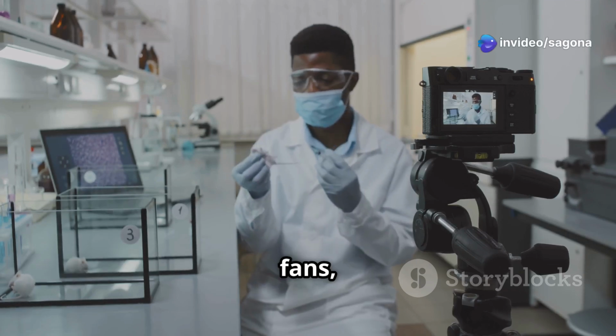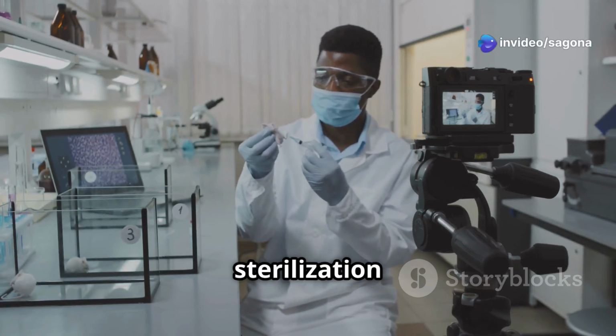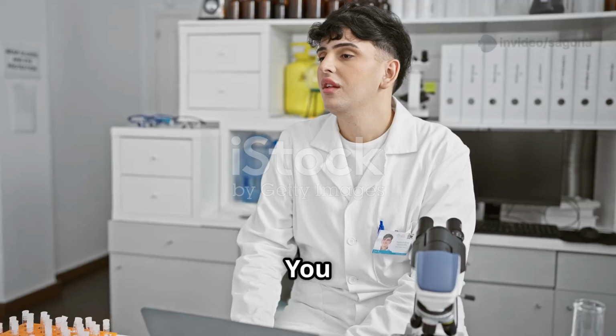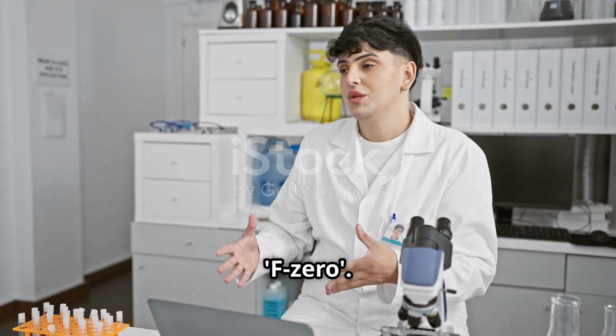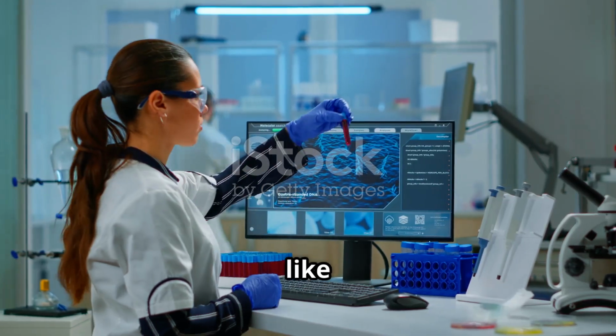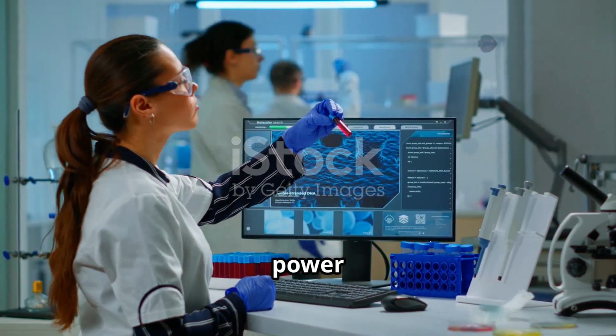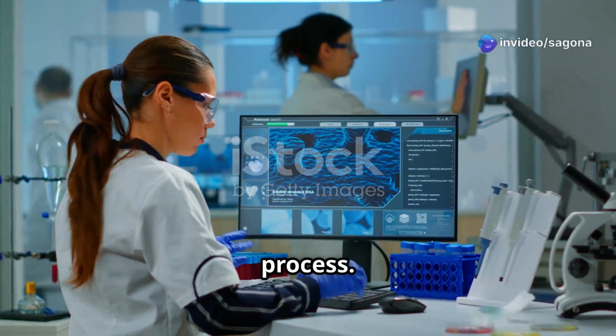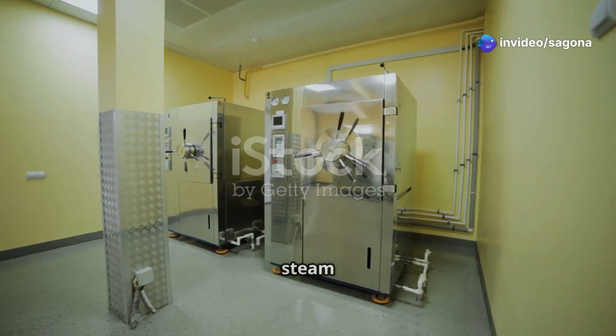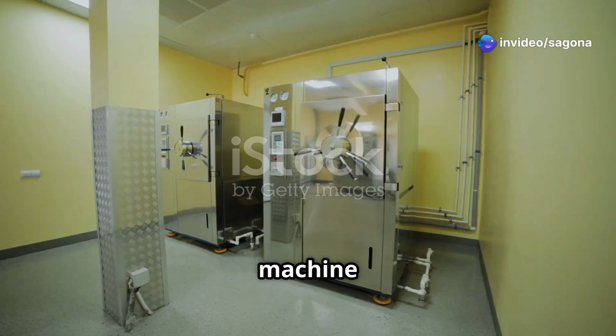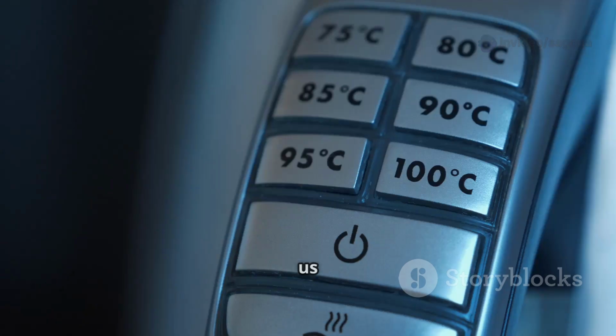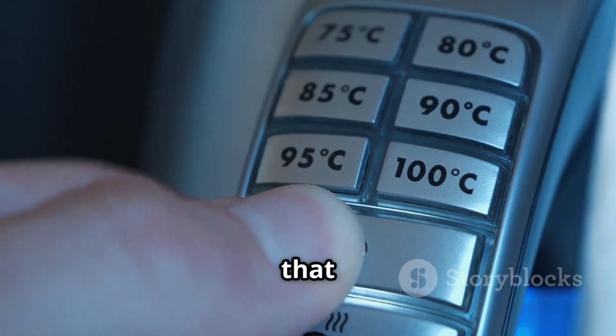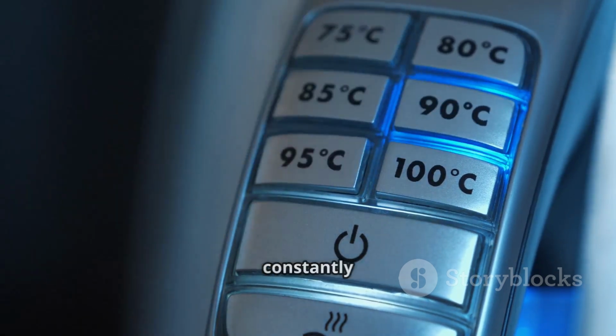All right, science fans, let's explore another key idea in sterilization, the F0 value. You might hear it called F-zero or F-naught. This F0 value is a bit like a score for the total killing power of a heat sterilization process. Specifically, it's used for steam sterilization, like in a machine called an autoclave. It tells us the equivalent time in minutes that the process would take if it was all done constantly at a reference temperature of 121 degrees Celsius.